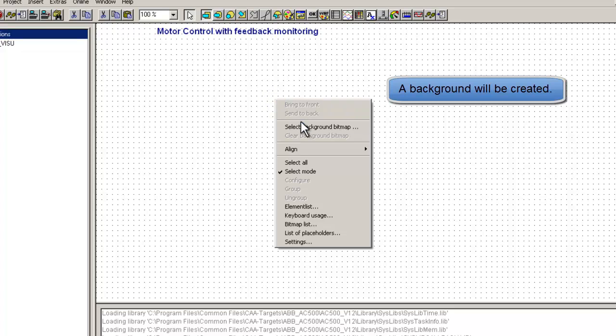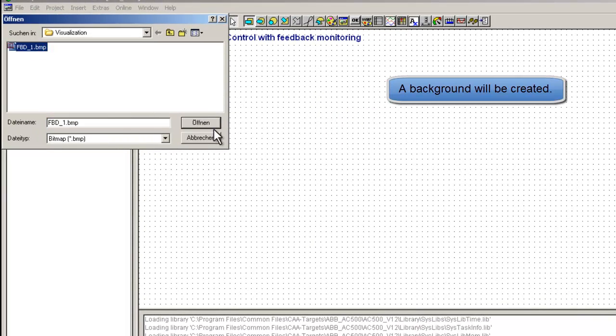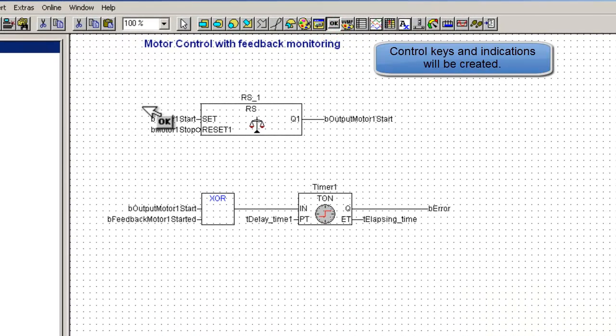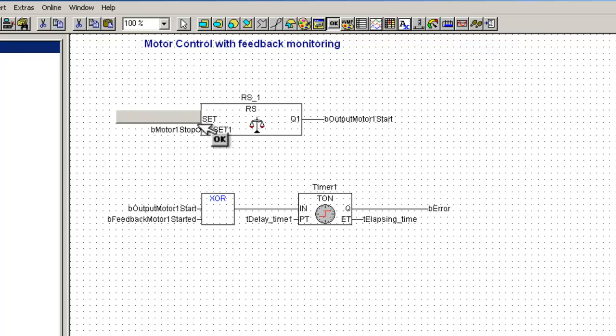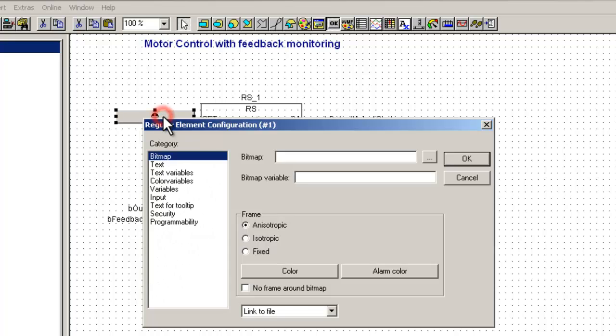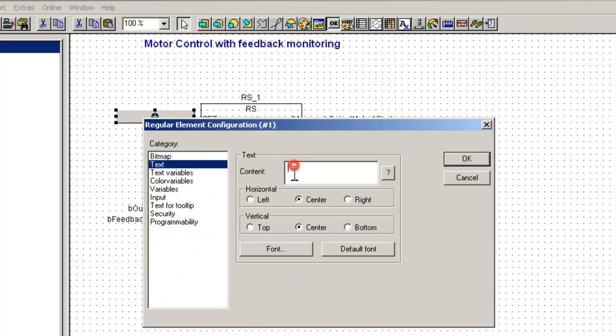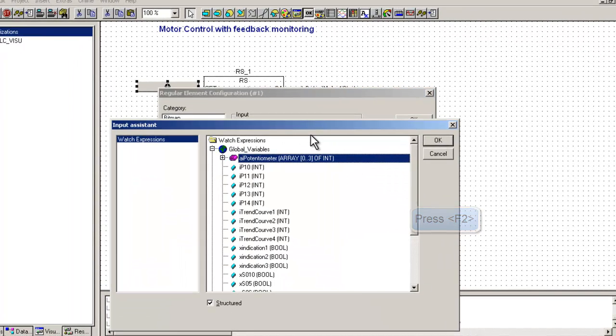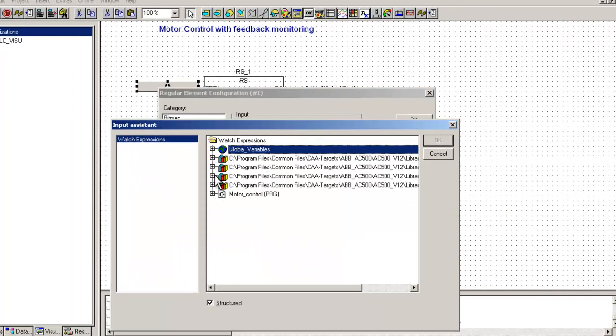We have also inserted a static background picture, already prepared to display the status of the motor running condition with color animation. Now we create two separate buttons to start and stop the motor. Buttons could easily be configured with actions like initiating or triggering some events from the visualization screen, in effect changing some tag or data values in the controller. In this example, the buttons are configured like push buttons, meaning pressing and depressing the button would send inverted boolean data to the controller.